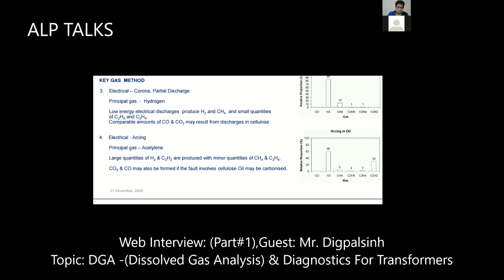But you have to note that in some cases the OLTC oil and the transformer oil mix up. Somehow they mix up, and in that case acetylene will be there, because in the OLTC compartment you will always find acetylene. The OLTC always changes its taps to 1, 2, 3 or any number of positions. When it changes the taps, a minor spark is produced inside the OLTC compartment. That spark or arc will generate acetylene. So if you find acetylene in the OLTC compartment, there is no need to worry. It will be there.